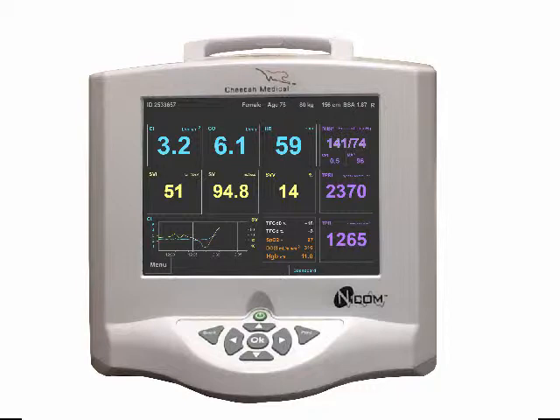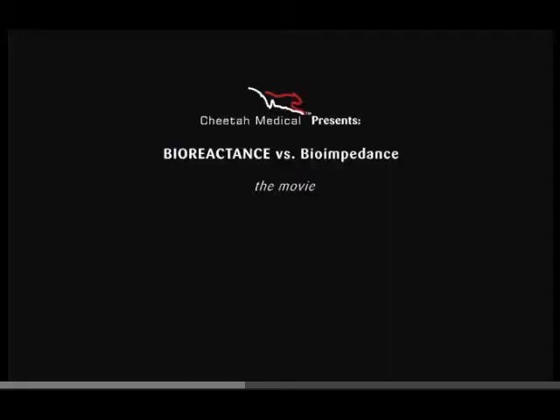Although calculations could be obtained by applying only 2 sensors on one side of the thorax, the NICOM system uses 2 sensors on each side of the chest and then averages the stroke volume measurements, effectively doubling the data used to make the calculations. Cheetah provides the following animation to depict the difference between measurements based on frequency and amplitude and the difference between bioreactance and bioimpedance measurements.